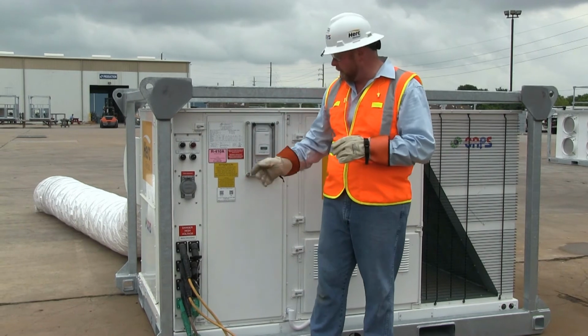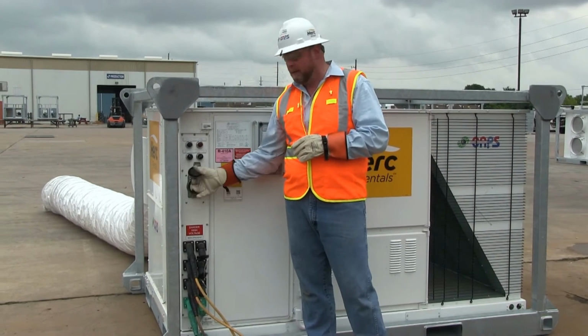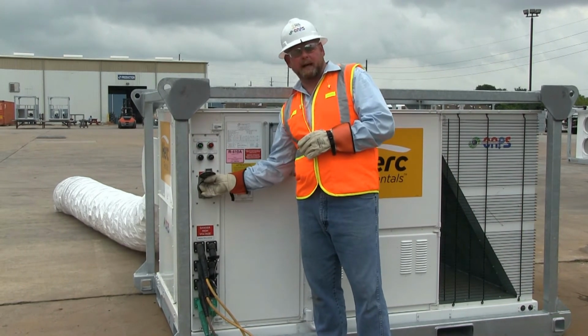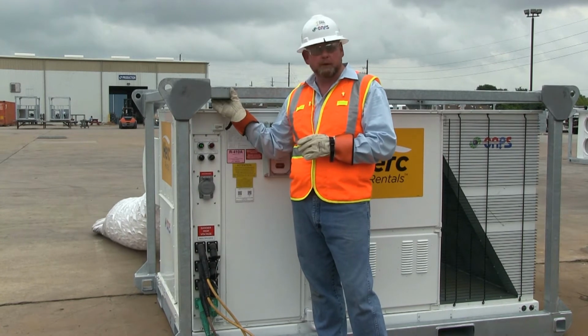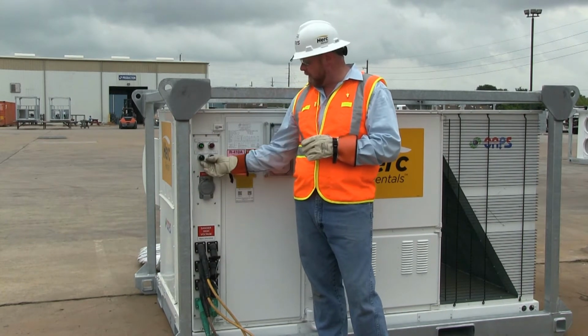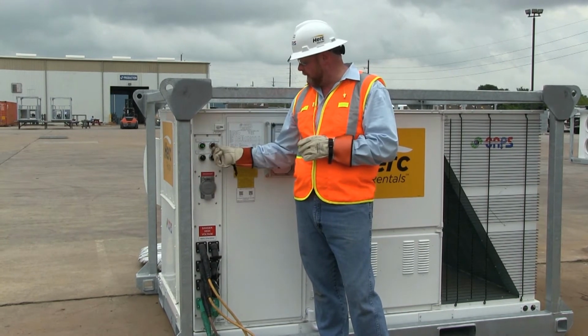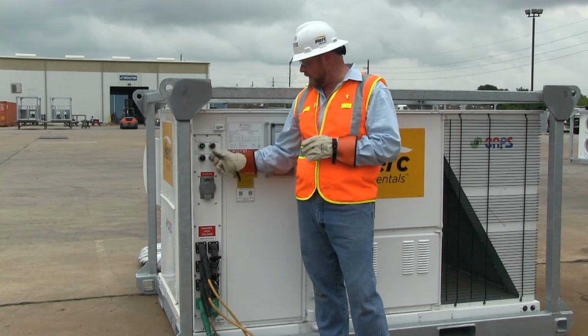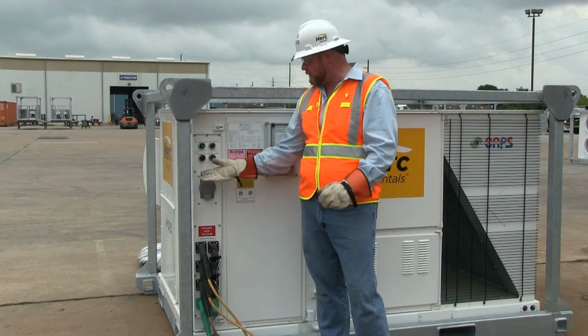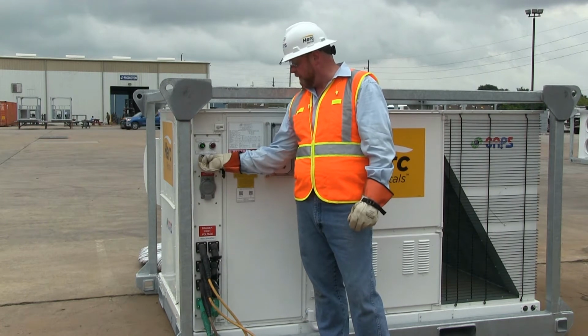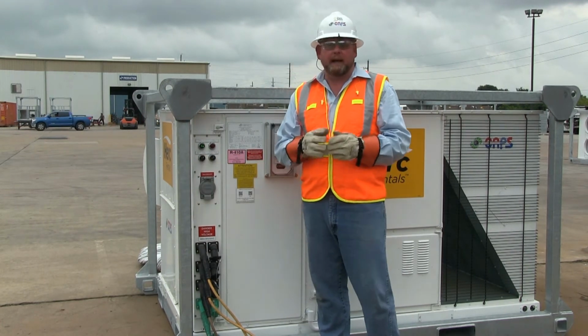We're going to start by simply going to the main circuit breaker here, and we're going to energize main power. The interior blower starts. Then we're going to look at our power switch. Light is on, in phase incorrect, light is off. That's correct.